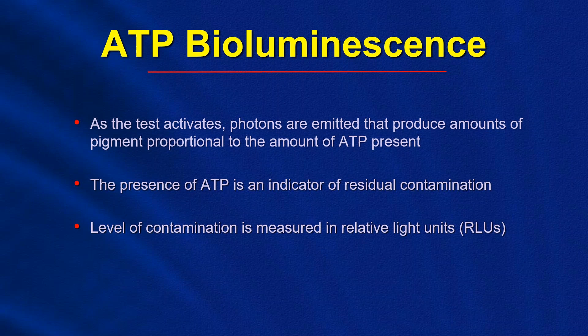So what are some of the benefits of ATP testing? Well, it is a confirmation of the cleanliness of your surfaces, your instruments, your endoscopes, the environment, whatever you happen to be testing with the ATP device, thereby reducing the risk of cross-contamination between patients. Again, you're checking for your cleanliness. How good a job did we do cleaning? You have the ability to track and monitor cleaning practices. So these devices can be programmed to track and monitor cleaning practices.